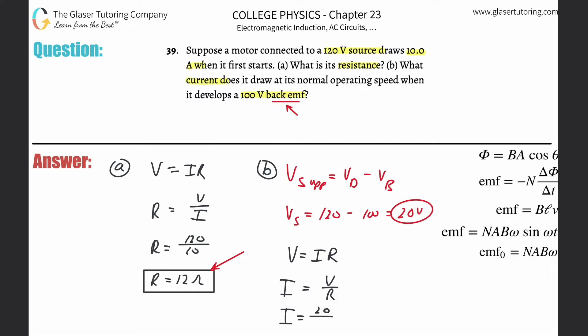And since we know all the values, we're going to plug them in. So this is 20, this is 12, and let's see what we get. So it's 20 then divided by 12, and we get a value of about 1.67 or so. 1.67. And that's in terms of amps now. So that's the actual amount of current when it's at normal operating speed.